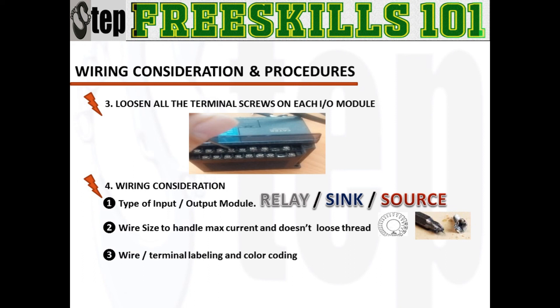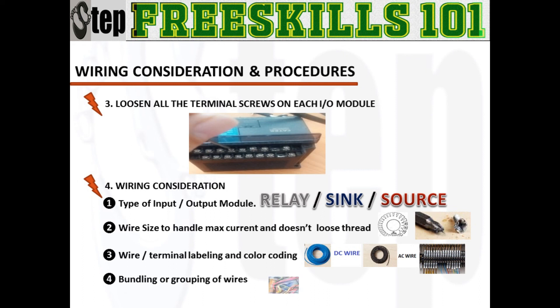Third, labeling of wires and termination, and using color coding, are important for identification especially during troubleshooting and tracing. It is best to use shrink tubing or tape. The wires that will be connected to a single module must be bundled, generally using a tie wrap, and then routed through the duct with other bundles of wire with the same signal characteristics. Input, power, and output bundles carrying the same type of signals should be kept in separate ducts when possible, to avoid interference.